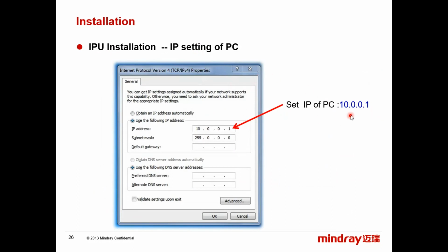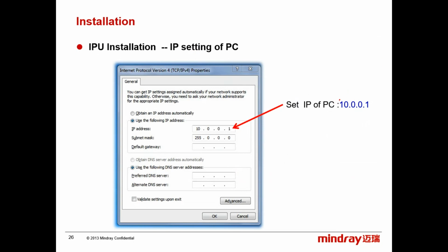Okay, when it is installed, here the IP address settings, make sure to be in the same range. You are not obliged to use one. You can use 2, 3, 4, 5, but you just do not use 7. 0.7 is reserved for the analyzer. So this is the range, it must be the same range. This one at the end you can use anything except 7. 7 belongs to the analyzer.